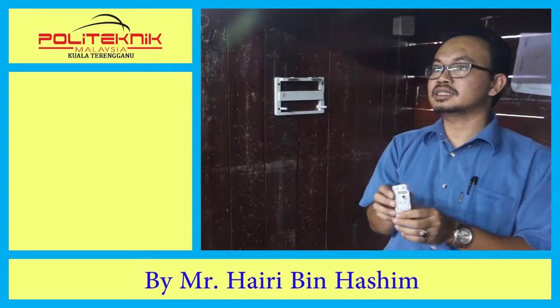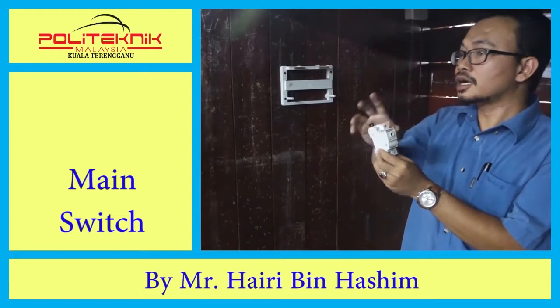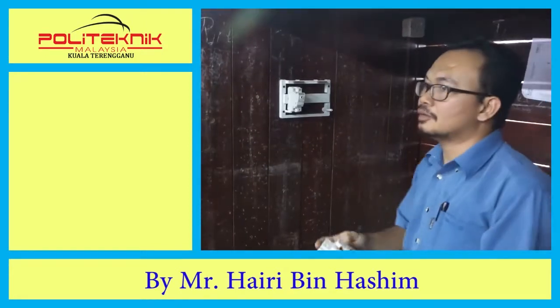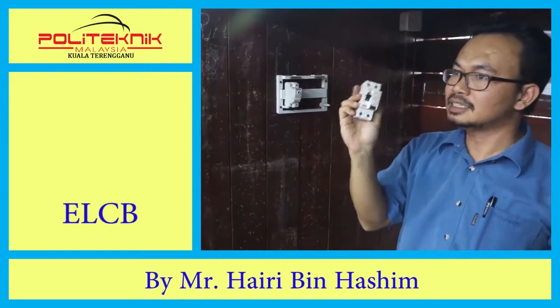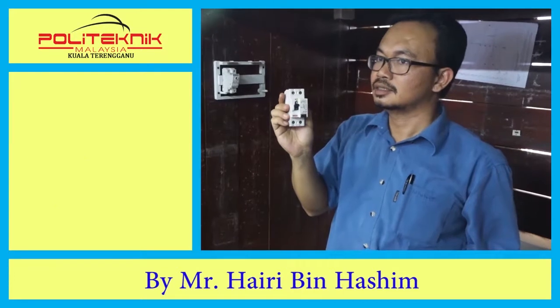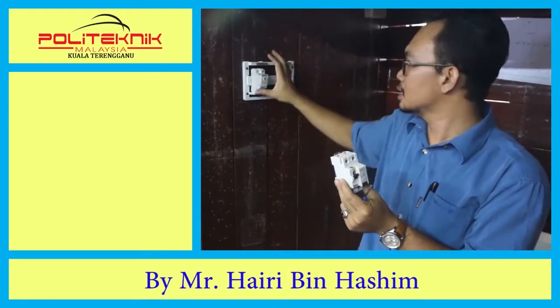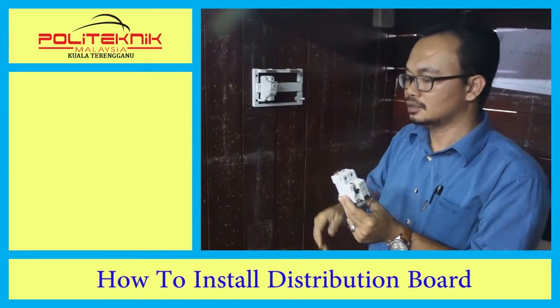With me here is the main switch. For a distribution board, after the kilowatt hour meter, it must go through the main switch. After that we're going to install ELCB or RCCB. ELCB is earth leakage circuit breaker, which means that if there is any leaking current, it will break the connection, and then the current will go to earth.